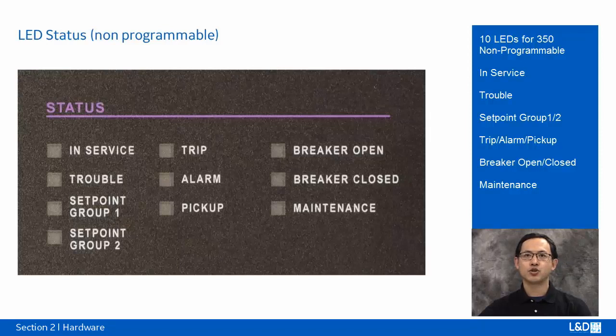Breaker status indication is based on the breaker's 52A and 52B contacts. With both contacts wired to the relay, closed breaker status is determined by closed 52A contact and opened 52B contact. Vice versa, the open breaker status is determined by opened 52A and closed 52B contacts. If both 52A and 52B contacts are open or closed, the breaker is racked out of the switchgear.